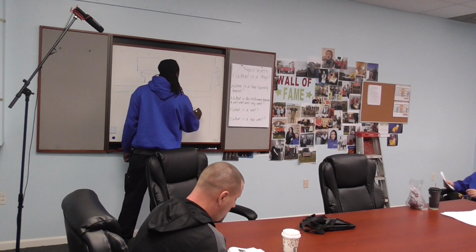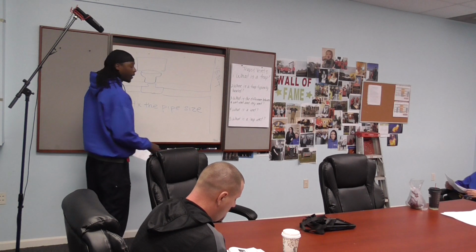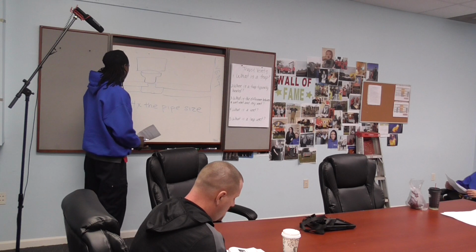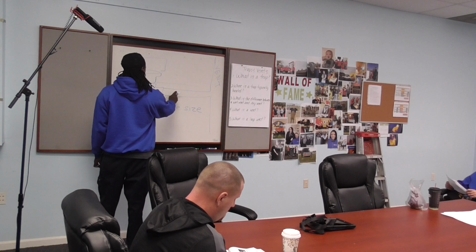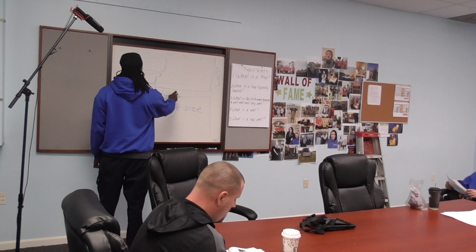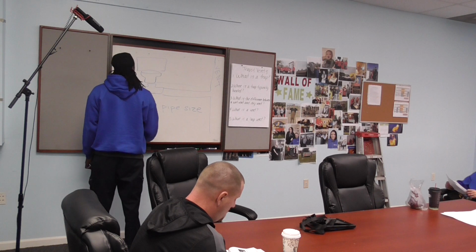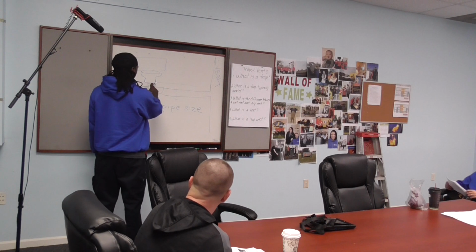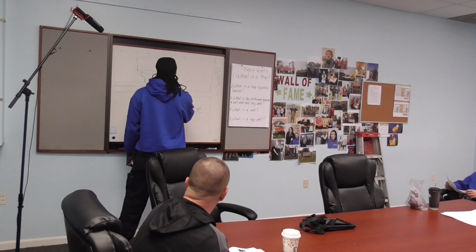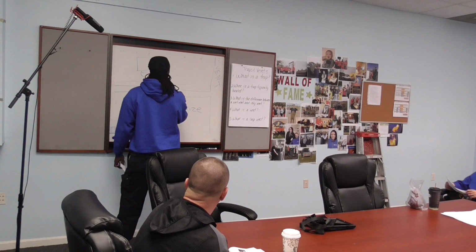Is that vent just going straight outside? Yes. Bend out your roof. So let's say it's 3 inch. We typically use 3-inch pipe on a toilet. So that's 12 feet. That's how far away your vent can be from this drain. So you will start from this drain, and then you will measure all the way over to where your vent starts. That's how far away your vent can be from you. If it's more, then you have to use another vent.